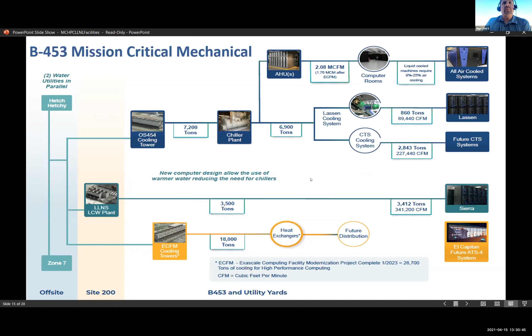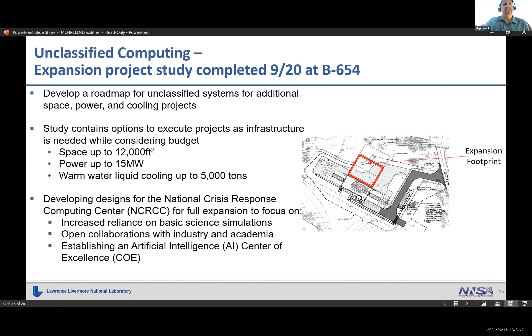And at another facility, we have just straight adiabatic cooling, which is a little bit more complicated because you are relying on the wet bulb temperature. So on those high humid days, it could be a challenge. But our air handlers in that building serve 2 purposes. They have liquid cooling capabilities as well as air cooling. And that's our facility, building 654. It was built modularly, so it can expand out to the north when we can knock out that wall and then expand our facility as we grow.